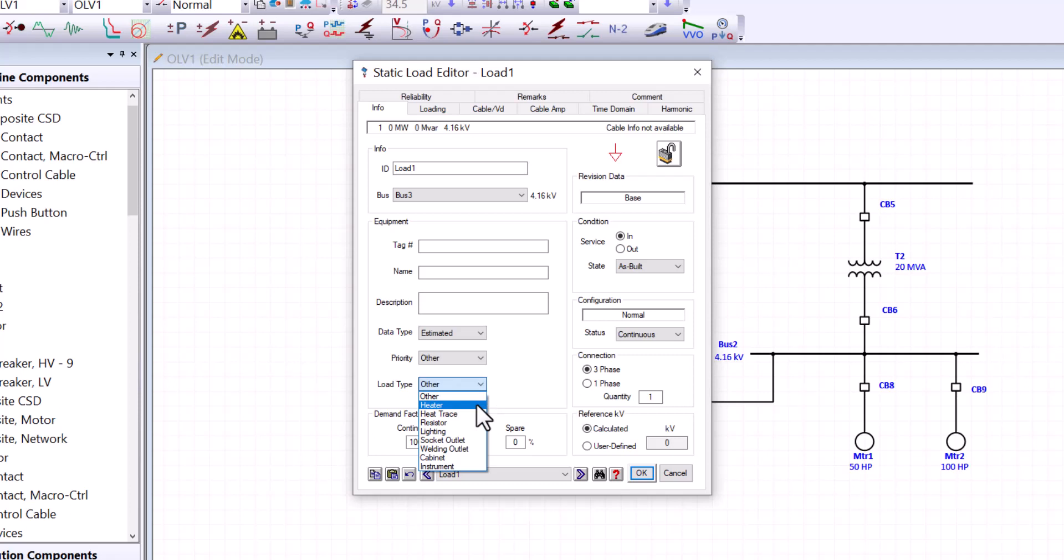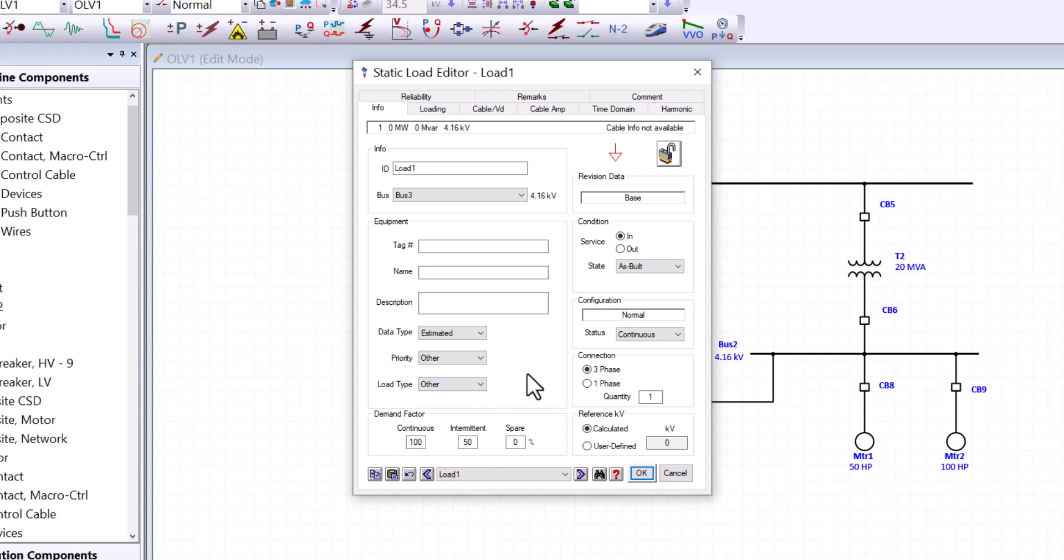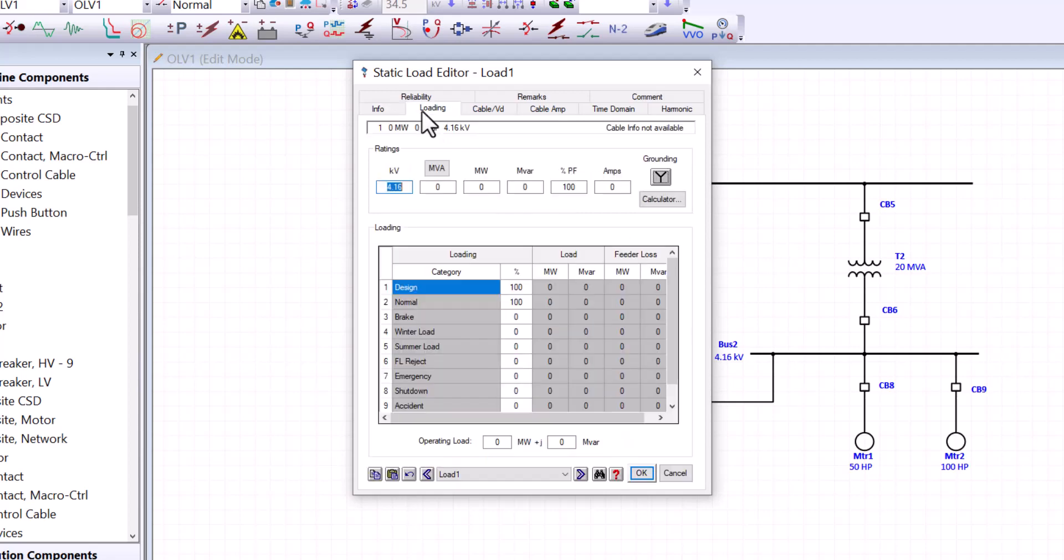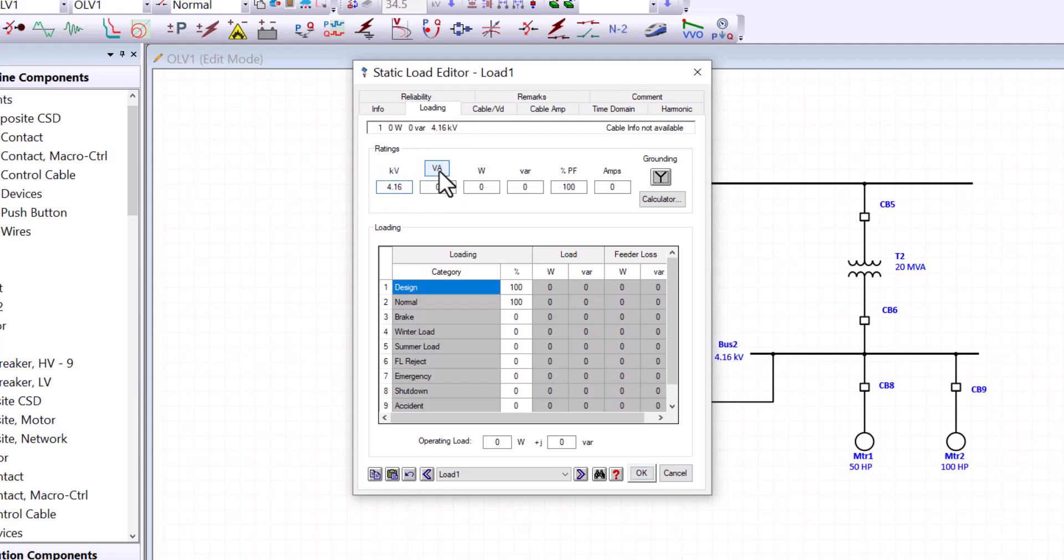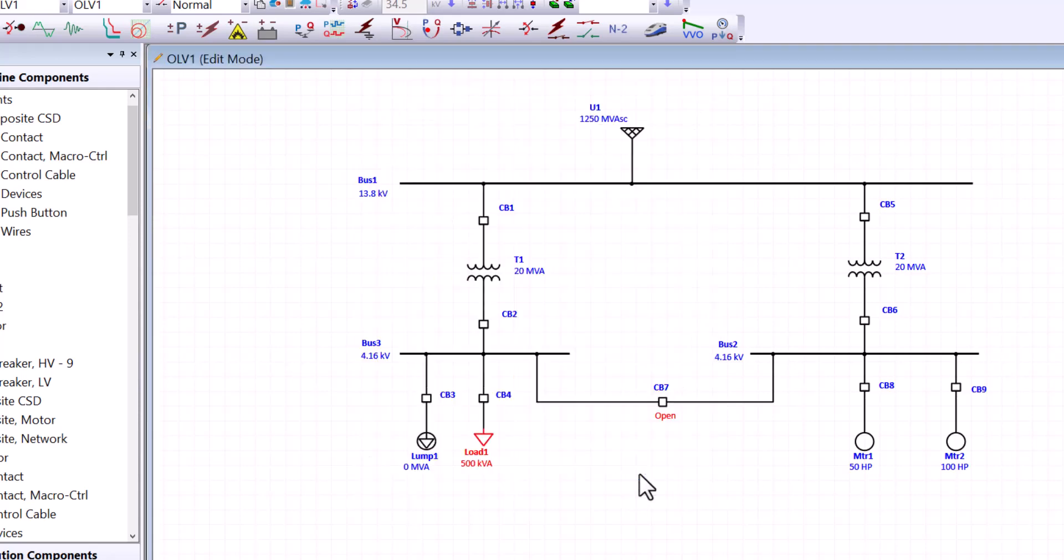This would provide us with some good examples. Like heaters, heat trace, resistors, lighting, socket outlets, and so forth. These can be used as static loads. And for the purpose of our example, we need to go to loading. These are connected to 4.16 KV bus. And we are going to toggle the rating to KVA and enter 500 KVA. And that's all what we need for static load.